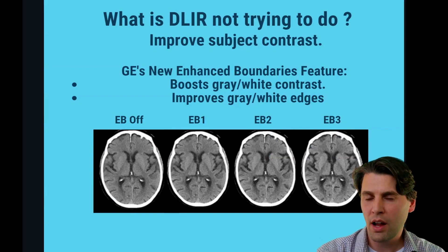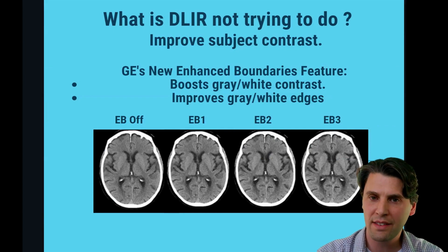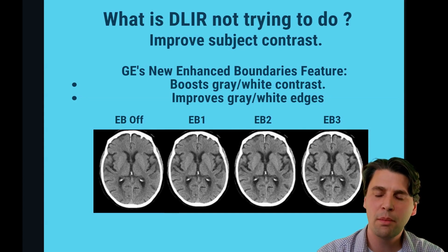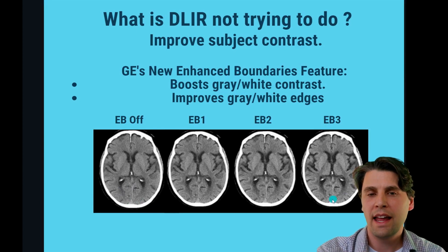Finally, I want to summarize and clarify what we're not trying to do here. With the deep learning network currently, we are not trying to modify the physics of the system, and we are also not trying to change the contrast. The network for deep learning on the system today is trying to estimate and reduce the image noise — we're not trying to change the contrast in the image. There are methods to modify the contrast as well as the edge definition between gray and white matter. One recently introduced by GE Healthcare is called enhanced boundaries, where you can see the CT number difference between gray and white matter is more accentuated and the boundaries are better visualized with the new EB3 option.